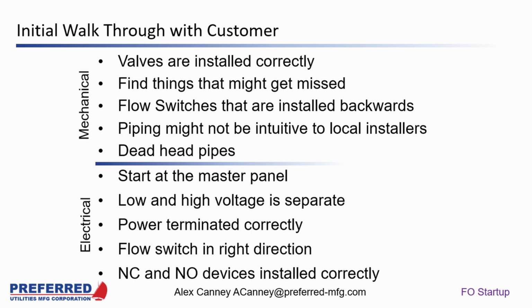That was a story I used to illustrate the importance of walking off the system. I basically took a look at the return lines, knowing that if the relief valves are going into the return line, in most systems they go all the way back to the main tank. In this case, as I followed the return line back, it didn't actually make it there. The main tanks were located outside the building, and before the return line got all the way back to the building envelope, it was just capped off. That presents a real problem because now we have no way to bleed off fuel on an overpressure. So that was really just as simple as looking at the piping.